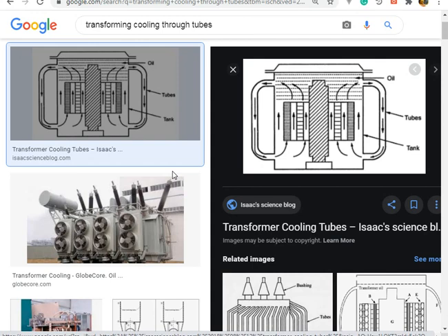It is going to dissipate by convection, and it is also going to dissipate by radiation. So 12.5 watts per meter square per degree centigrade is the total energy dissipated there. And when it falls down through the tubes and comes back inside the tank, it is cooled down. So what you are doing here is that your tubes are adding a little bit of surface area.